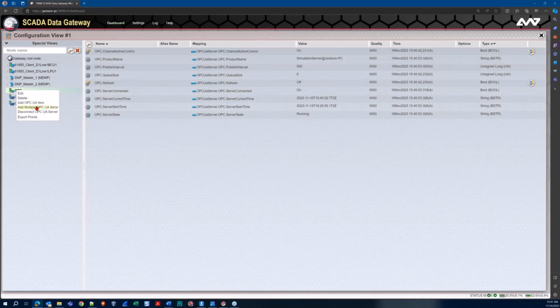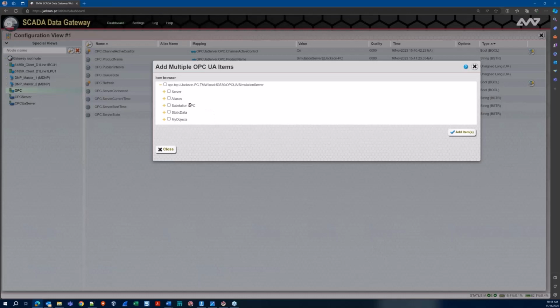So now it's time to start adding items to my OPC UA client. There's a couple different ways to do this. I can add individual points or multiple points, but either way, one of the nice things about OPC UA, or OPC in general, is that it's a browsable protocol. So I don't need to memorize point lists or provide a configuration file. I can just click and add, browse my device, assuming it's available and connected, and see what data points are available on it.